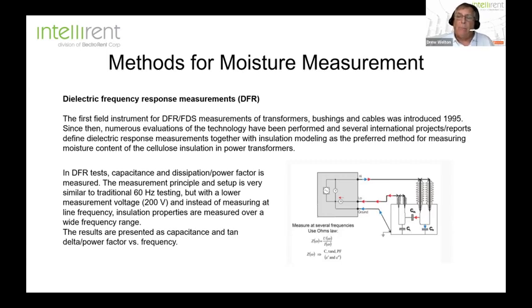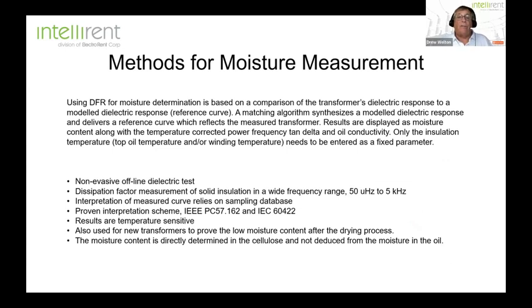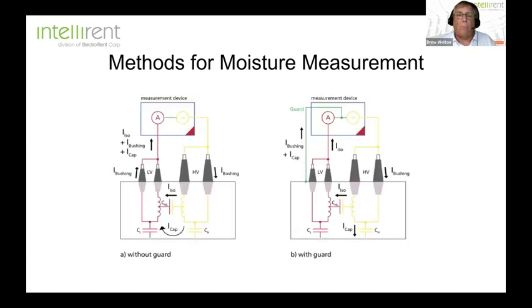Under laboratory conditions, they knew how much moisture, in percentage, they embedded into these samples, and then ran this test on them to see what the geometry of the response curve looked like under certain conditions. It was pretty amazing how accurate it was, looking at the model that it produced in these curves and equating that to the moisture percentage in the solid insulation. So this was quickly accepted into industry standards by both CIGRE and IEEE. There have been IEEE working groups on the Transformers Committee, which I've been on for about 8 years, and they have really narrowed down the modeling to be very, very accurate in determining the percentage of moisture in the insulation.